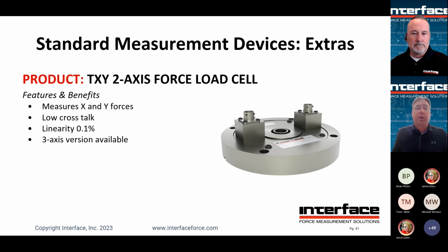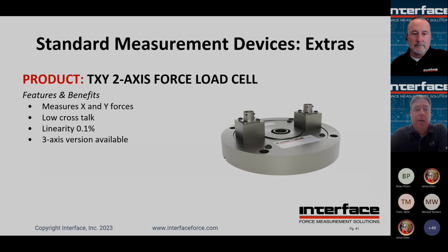This is a load cell that's very specific. This is our model TXY. It's measuring X and Y forces, with very low crosstalk and very good linearity performance down to 0.1%. And we also manufacture a version of this that's going to have a Z axis as well. This is very common for tire testing applications. There's a center bearing there that can be mounted so you can measure a downwards force and force at 90 degrees to that.